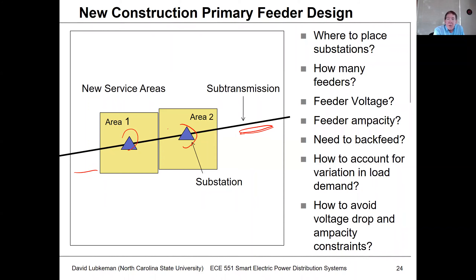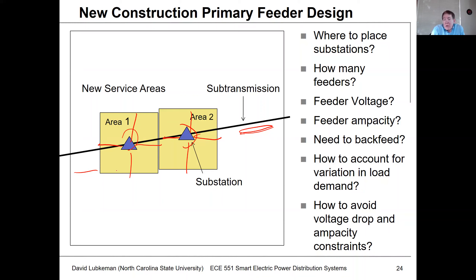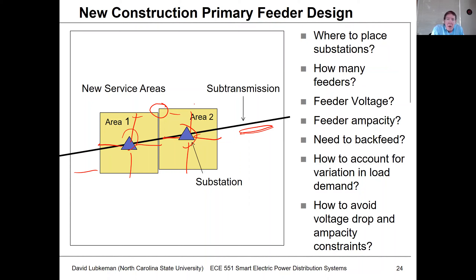You need to figure out where the substations go, how many feeders you're going to have, and how you're going to route these feeders within these areas. You need to know what type of feeder voltage to use and what feeder ampacities in terms of current ratings need to be supported. You need to be able to backfeed, so if you have load, does it need to be served from either substation? You need some way of calculating what the net load is going to be in each area based on possible land use, to set up a feeder infrastructure without issues like voltage drop and ampacity limits.